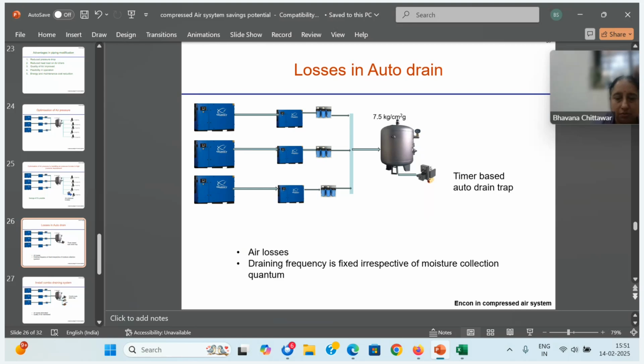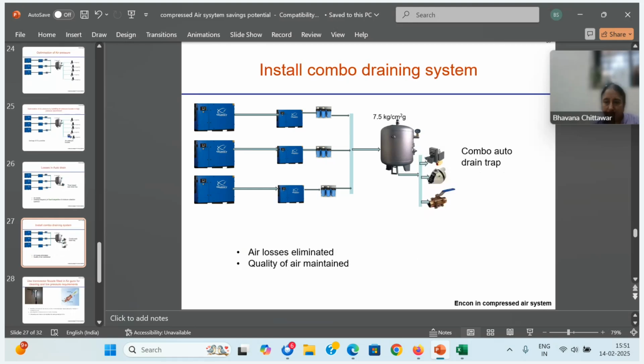Generally, most customers go for auto drain traps. Here their losses are more, because along with the condensate, air is also getting drained. So you go for a combo auto drain trap. What is a combo auto drain trap? It will have 3 types of trap. One, a manual drain for periodical checking, whether the traps are working or not; once in a day, you can manually open and close. Then a float type trap, which will drain regularly without loss. Then a timer based trap, which is set for once in an hour or once in 2 hours for a few seconds. This will reduce your overall losses. A huge amount of savings can be achieved.